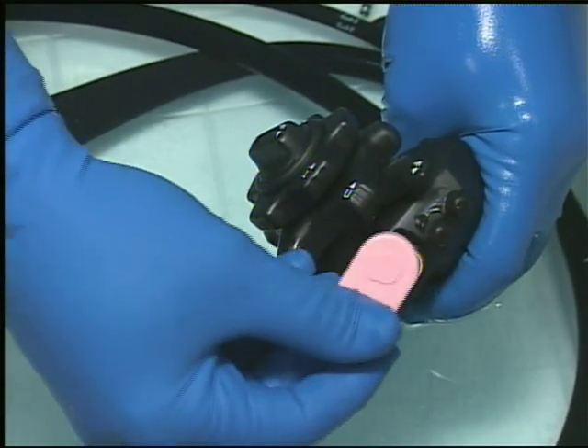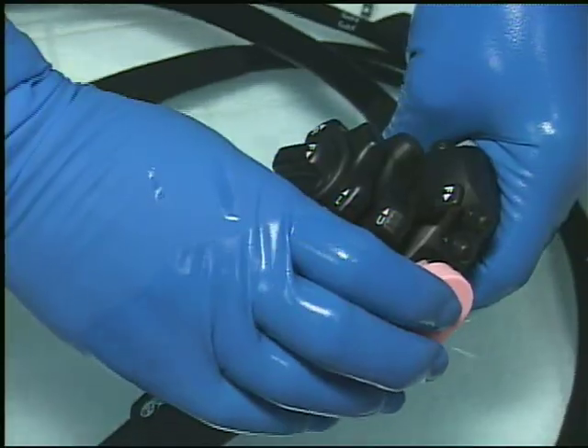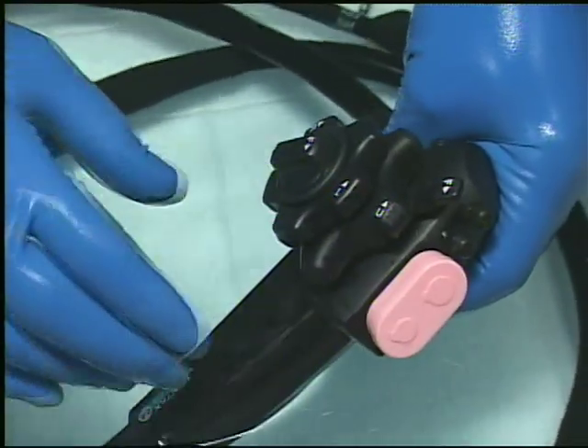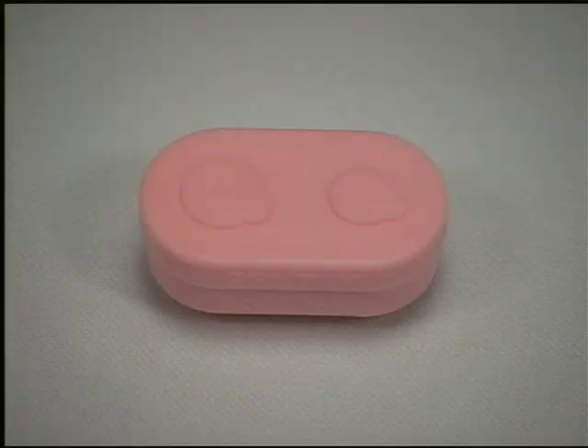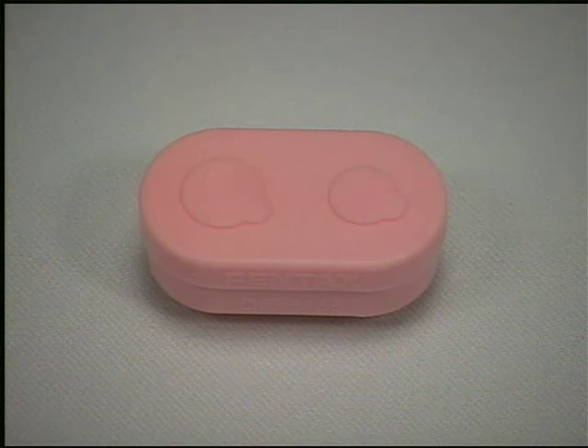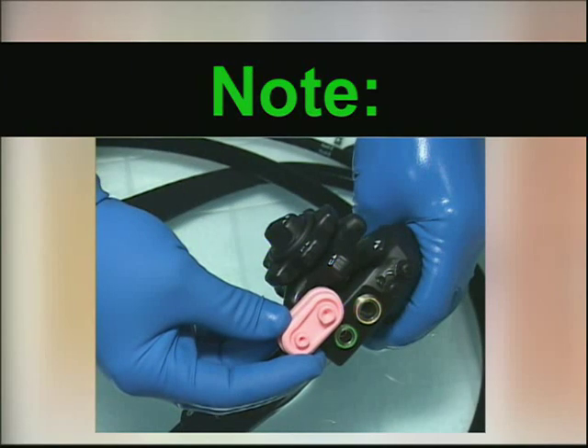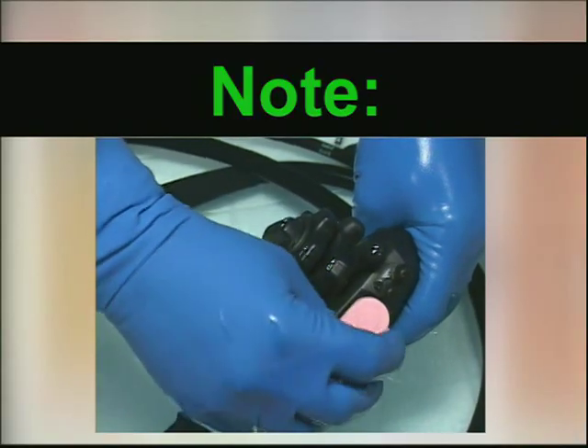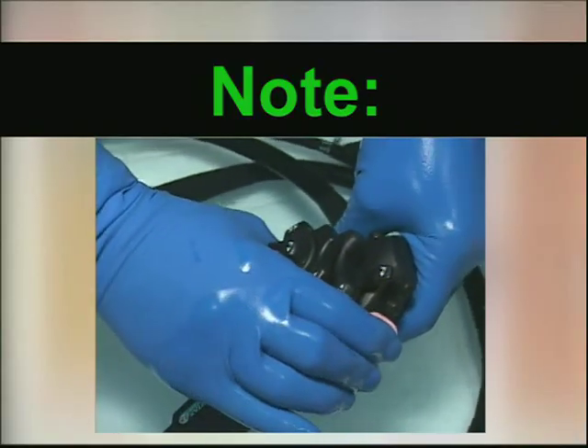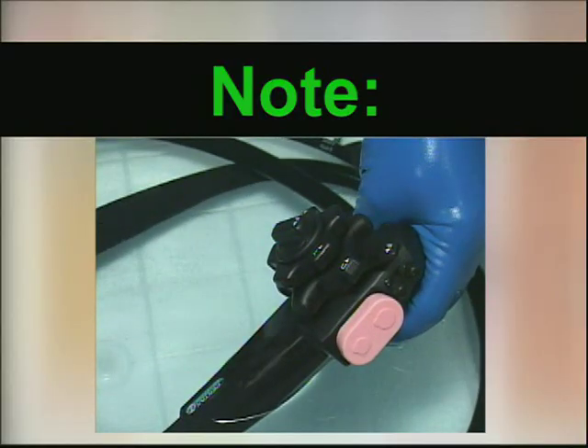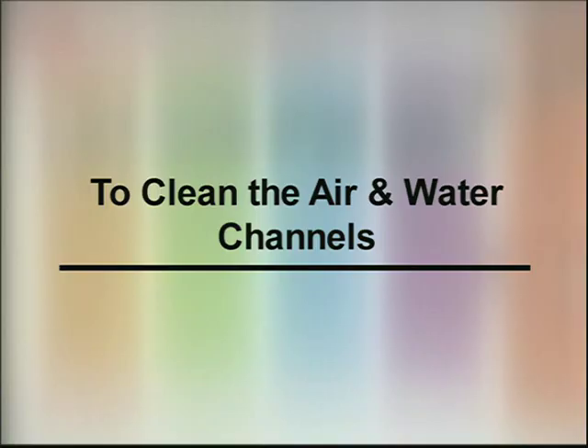This adapter caps or seals off the air-water and suction cylinders to allow for unidirectional flow of solution through these channels. Note that the symbols on the OFB166 show two circles, which represents the shape of the respective cylinders for proper attachment. Note: it is imperative that the OFB166 channel cleaning adapter is securely attached to the respective cylinders. Failure to properly match and secure the cleaning adapter could result in ineffective and incomplete reprocessing. To clean the air and water channels.